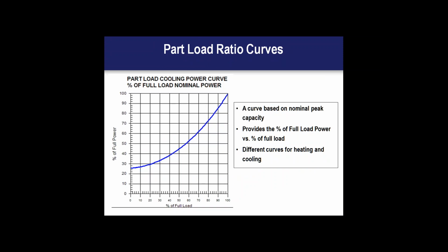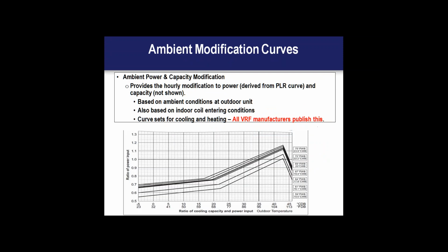Again, this really isn't anything new. The part load ratio curve is percentage of full power versus percent of full load. You'll see this for cooling; it's a nominal curve based on a 95-degree test condition. And there will also be a curve for heating part load operation, which is typically based on a nominal 47-degree day. All manufacturers then publish ambient modification curves, which have to be applied on top of those PLR curves. They may be in the form of graphs, a family of graphs or charts, or they may be tabulated values, depending on the manufacturer.